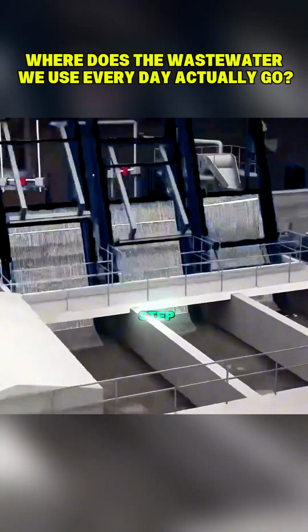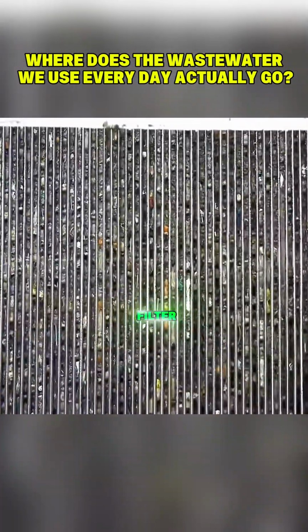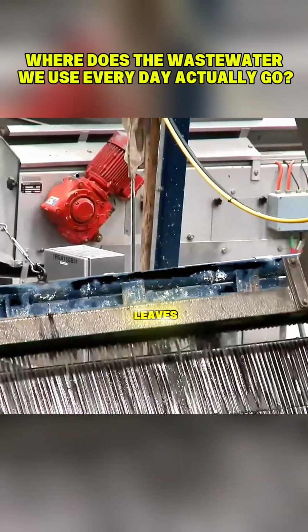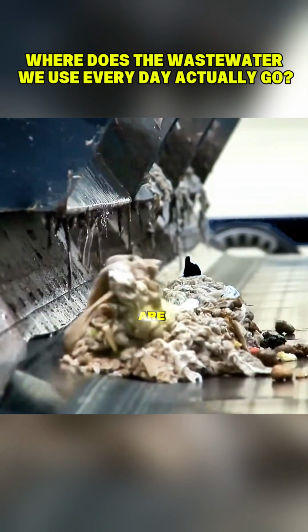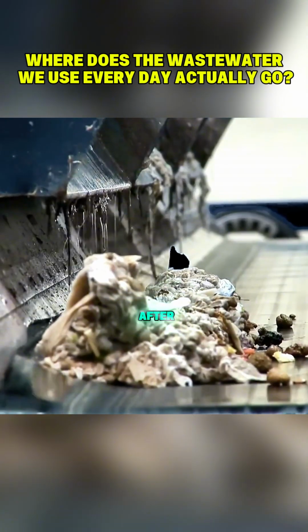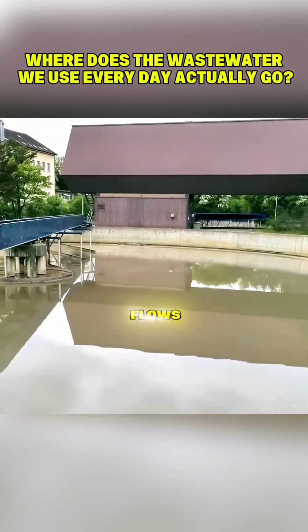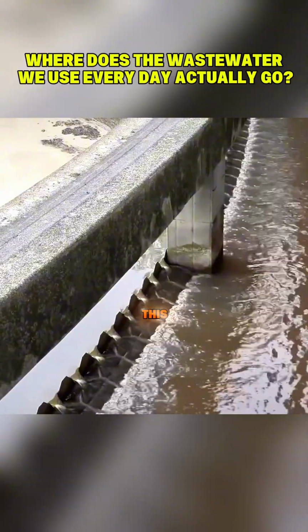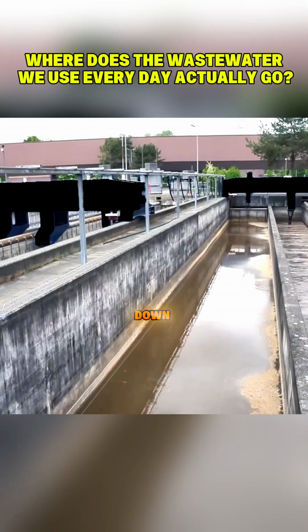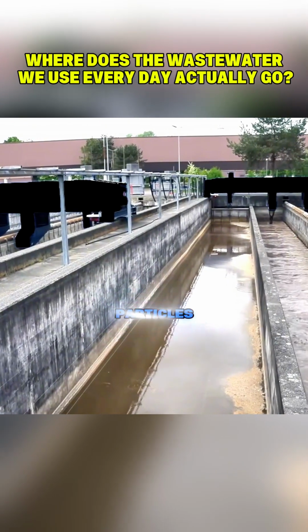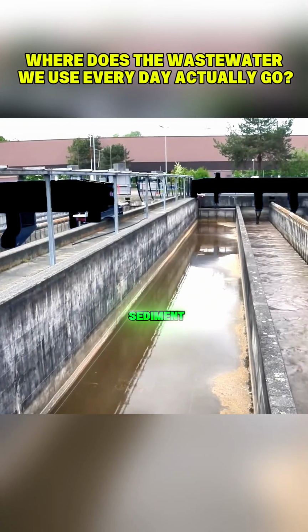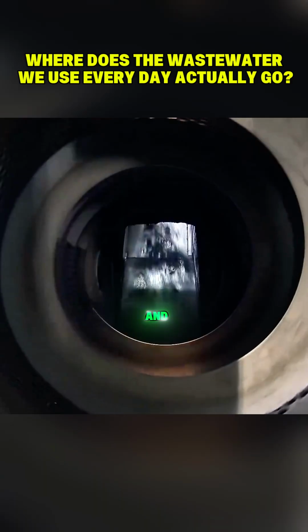The first step is filtration. A screen filter separates plastic bags, leaves, and various solid waste. The wastewater, after initial filtration, flows into a sedimentation tank. At this point, the water flow slows down, and sediment and particles settle to the bottom. The settled sediment is sucked into a separator for processing, while oils and foam on the water surface are removed.